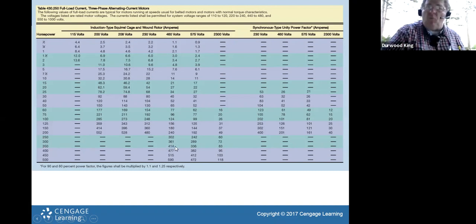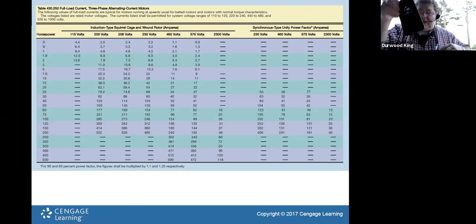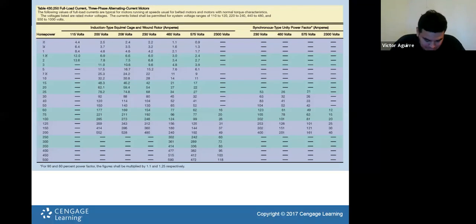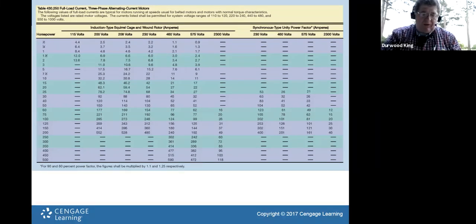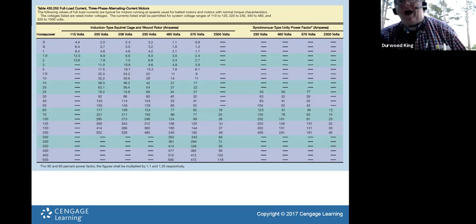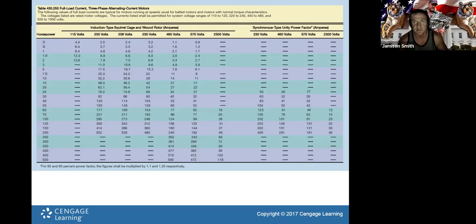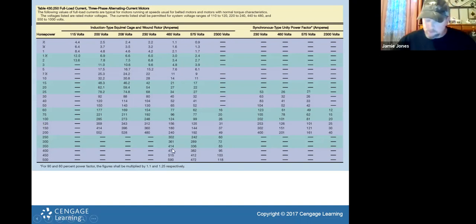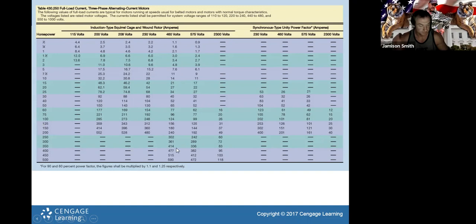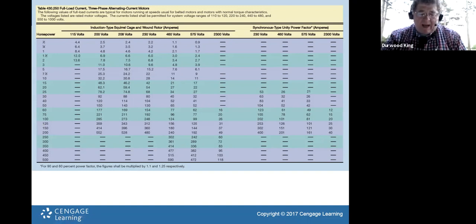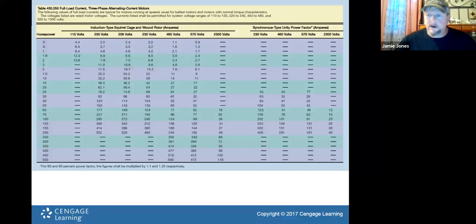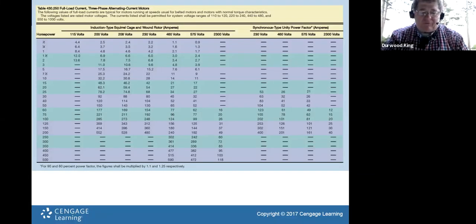Now we've got to take that times 1.25. Everybody get out your calculator and do this, because this is the important stuff here. Doing this can keep you from underrating wire and having an embarrassment later on with wire overheating and melting in conduit. 414 times 1.25 gives 517.5 amps. So you've got to go up, so it will be 518.